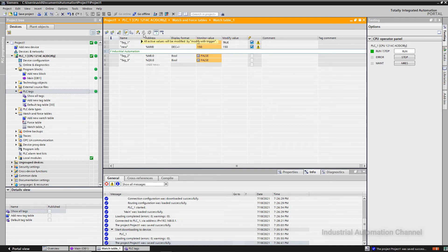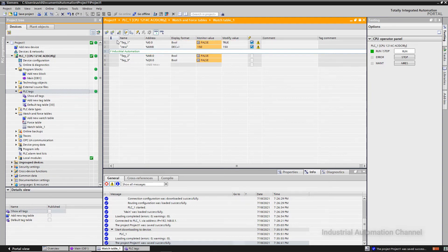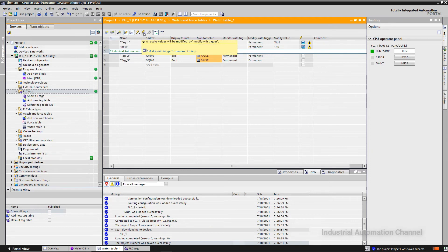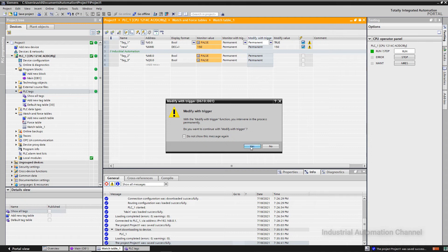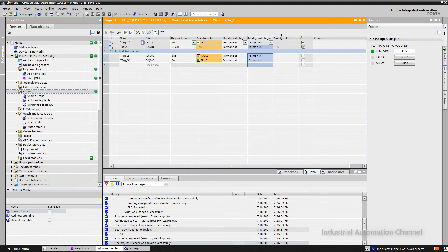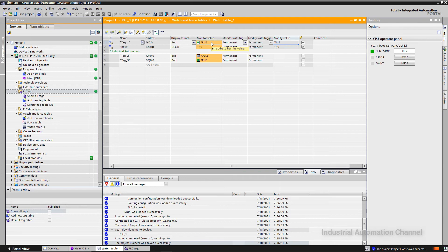The next button modifies all active values with a trigger, but it is deactivated by default. To activate it, press the 'show/hide expanded mode columns' button. If you press it, two more columns are added and 'modify with trigger' becomes activated. It asks if you want to modify with trigger — click yes. Now we push this value permanently into the variable using this trigger. This time it doesn't matter whether the hardware push button is pressed or not — we have overwritten it with the watch table permanently.